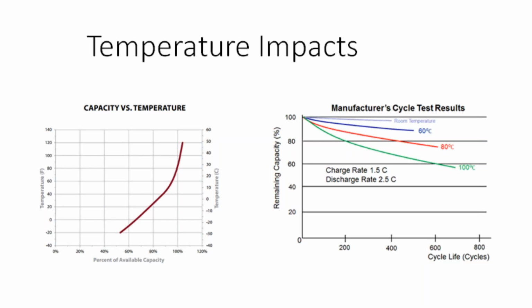In fact, I've even heard installers say that if you have your batteries in a hot box, but there's a concrete slab on the ground that might be cooler than the rest of the box, that temperature differential alone can degrade the batteries faster, because the bottom of the batteries would be cooler than the top. That causes different degradation rates within the battery itself. Usually a 12-volt flooded lead acid battery is comprised of multiple 2-volt cells. The cells at the top of the battery stack being hotter than the cells at the bottom being cooler have different electrical characteristics. That means they're going to age differently, and the cells are going to go bad a little bit faster than otherwise.